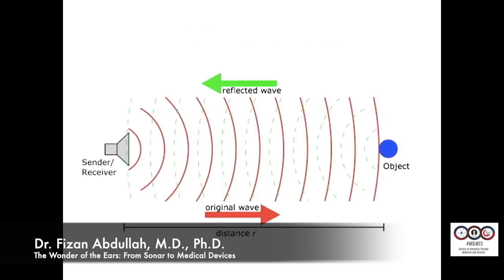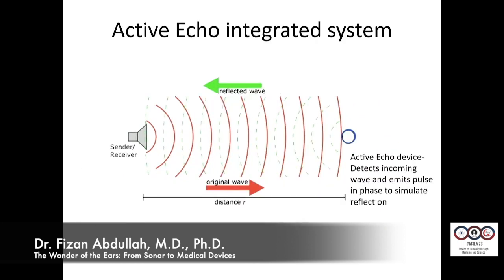So what we're talking about is that the ultrasound is on the left side. First of all, this is the standard way we do ultrasound. You have the ultrasound probe on the left side, it hits the tissue and it comes back and reflects. But the thought was, if you have a catheter or guide wire that otherwise does not reflect the sound, let's put an electrode on the other side and have it emit a sound so it makes the machine think it was bouncing off. It's almost faking it, so that the catheter, which previously could not be seen, can now be seen on an ultrasound.